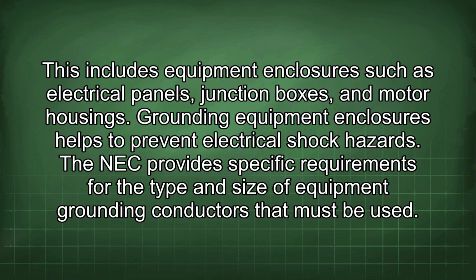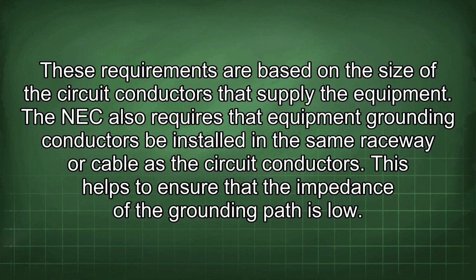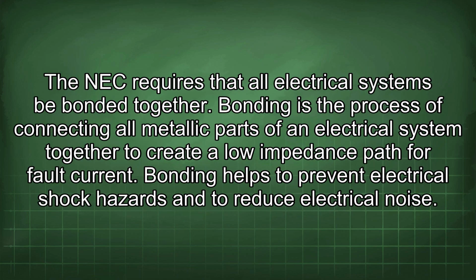Grounding equipment enclosures helps to prevent electrical shock hazards. The NEC provides specific requirements for the type and size of equipment grounding conductors that must be used. These requirements are based on the size of the circuit conductors that supply the equipment. The NEC also requires that equipment grounding conductors be installed in the same raceway or cable as the circuit conductors. This helps to ensure that the impedance of the grounding path is low. The NEC requires that all electrical systems be bonded together. Bonding is the process of connecting all metallic parts of an electrical system together to create a low impedance path for fault current. Bonding helps to prevent electrical shock hazards and to reduce electrical noise.